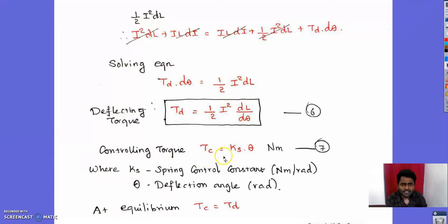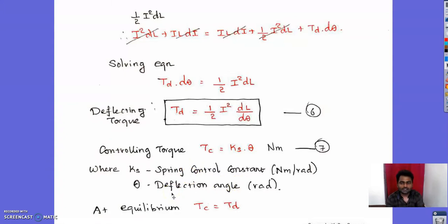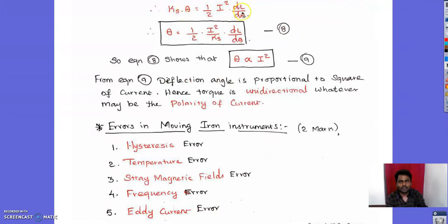The controlling torque Tc is produced by the spring, giving Tc = Ks·θ, where Ks is the spring control constant and θ is the deflection angle. At equilibrium, when the pointer comes to rest, controlling torque equals deflecting torque: Ks·θ = ½·I²·(dL/dθ). Therefore, θ = (I²)/(2·Ks) · (dL/dθ), showing that θ is directly proportional to I².